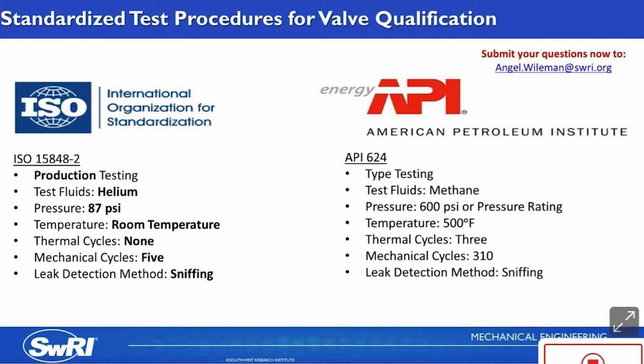The test fluid is methane gas and methane gas only, and this is a notable difference between the ISO standards. The standard references method 21, which is a leak check method established by the EPA for performing fugitive emissions testing, and it requires leakage measurement as a concentration in parts per million. Because of this, and because the procedures do not include a correlation between leak rate and sniff concentration, or between helium and methane test fluids, methane has been selected as the only approved gas for fugitive emissions testing, and this is a heavily debated topic.